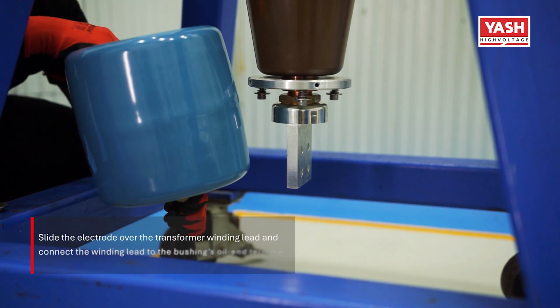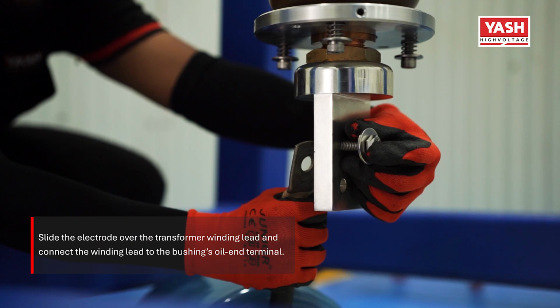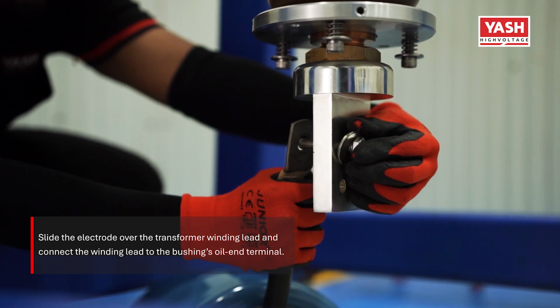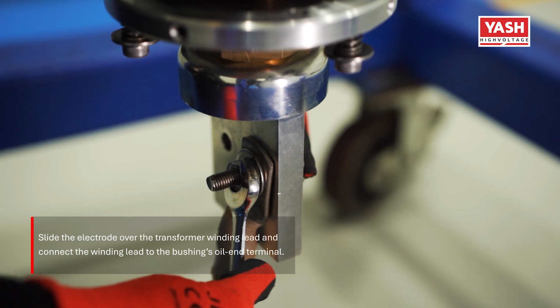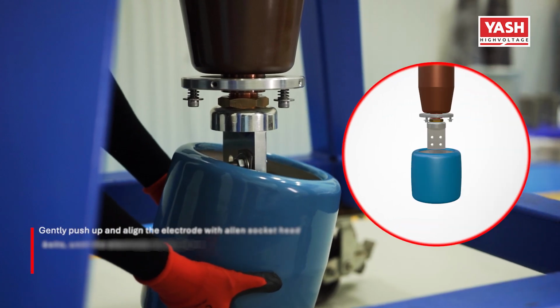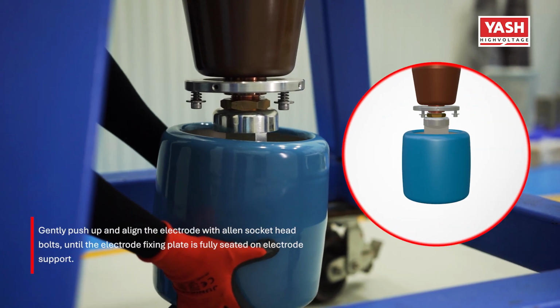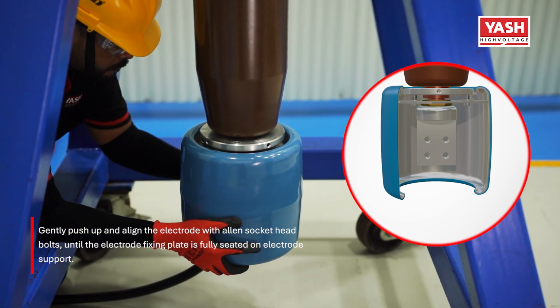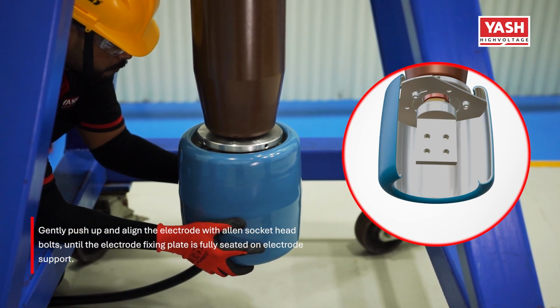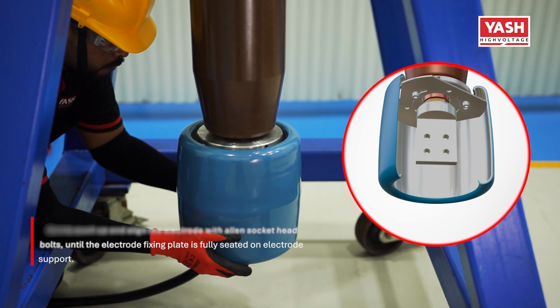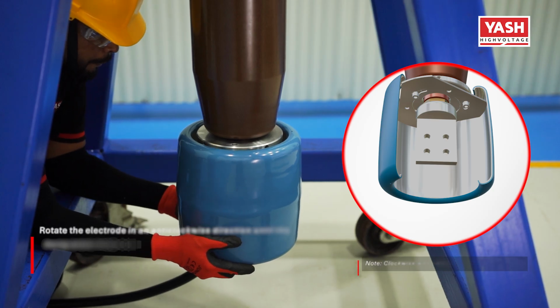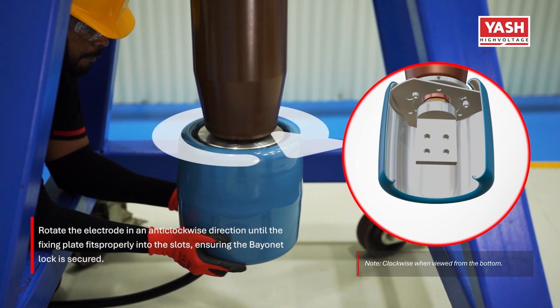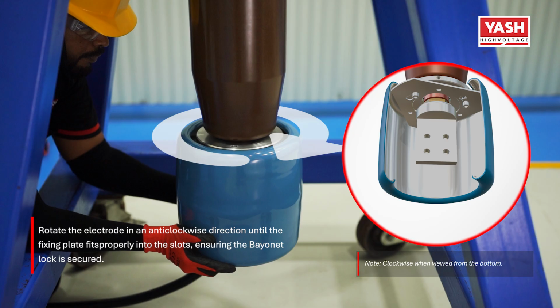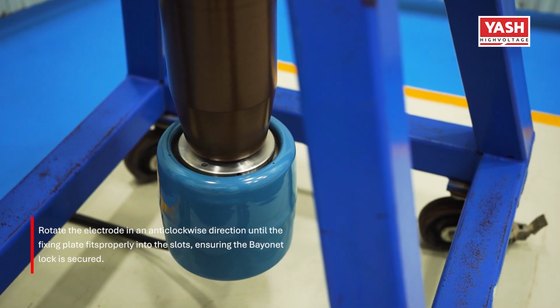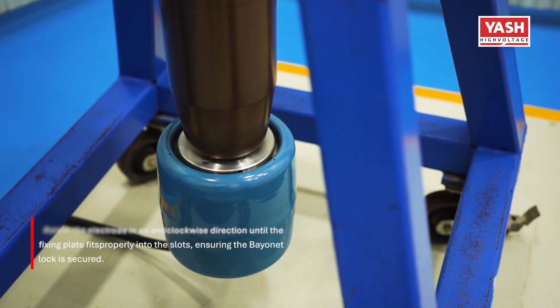Slide the electrode over the transformer winding lead and connect the winding lead to the bushing's oil end terminal. Gently push up and align the electrode with Allen socket head bolts until the electrode fixing plate is fully seated on electrode support. Rotate the electrode in an anti-clockwise direction until the fixing plate fits properly into the slots, ensuring the bayonet lock is secured.